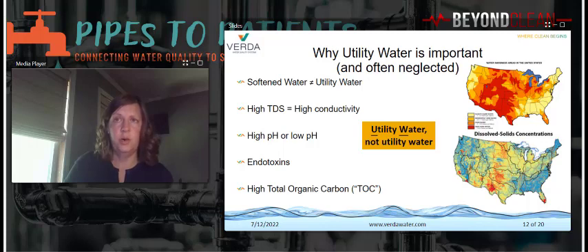Bacteria in chlorinated municipal water is usually at acceptable levels. However, endotoxin levels may not be. Some medical device polymers can absorb endotoxins. Hence, the use of utility water in early reprocessing steps could result in unacceptable endotoxin levels because the endotoxins may not wash off readily in later steps. Total organic carbon is another water quality parameter that can fluctuate across the seasons, getting higher in the summer months. Think of algae blooms in summer water supplies, and can impact the effectiveness of detergents and promote instrument staining.